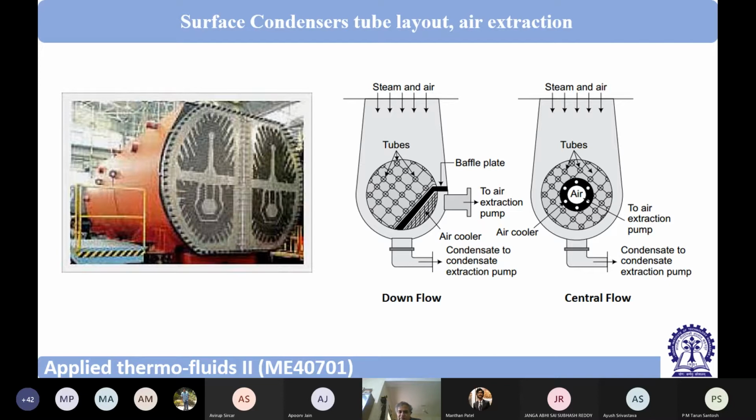Now, the water side heat transfer coefficient can be increased by increasing the flow rate with the help of a pump very easily. Steam side, that is not required. Whatever head or motive tendency it is carrying from the turbine, that is good enough for the mobility of steam.